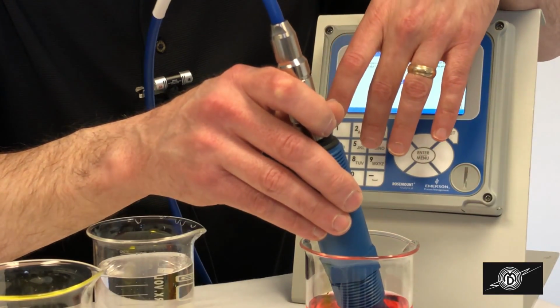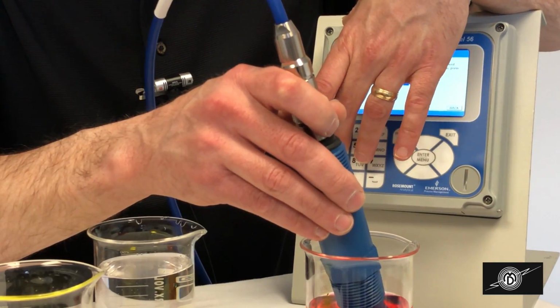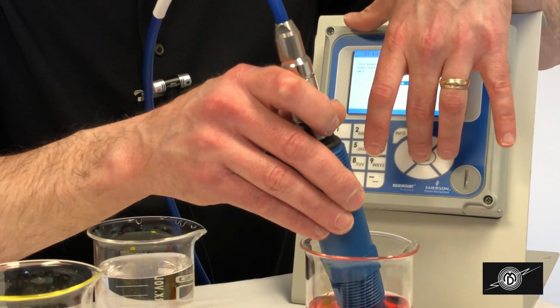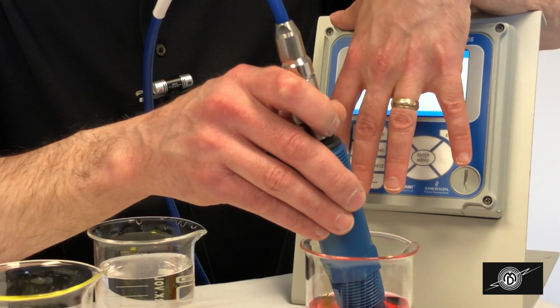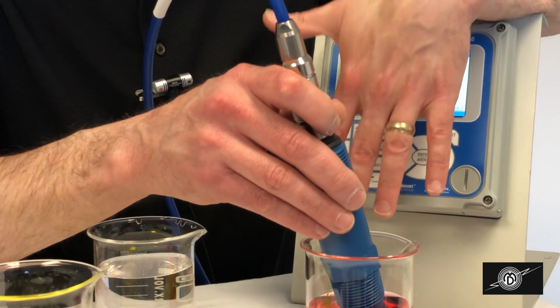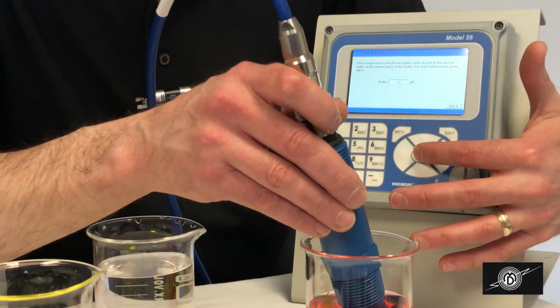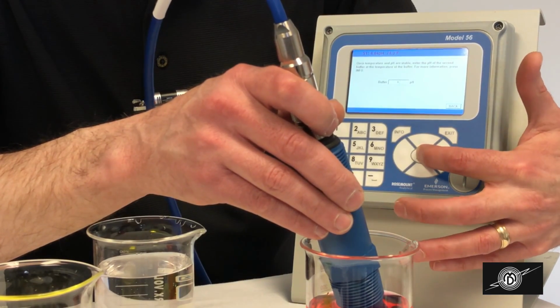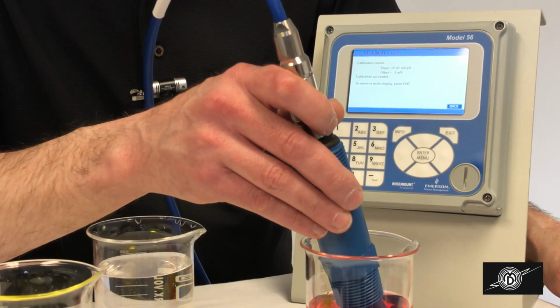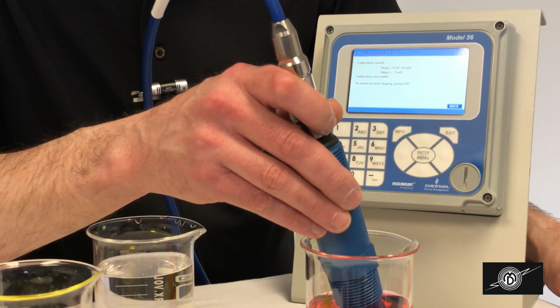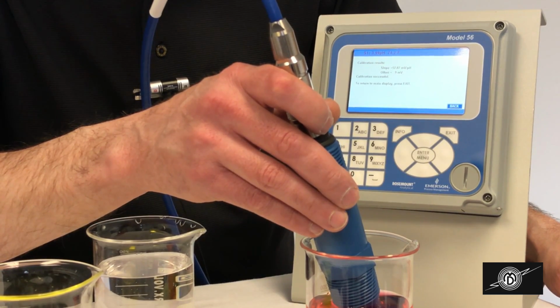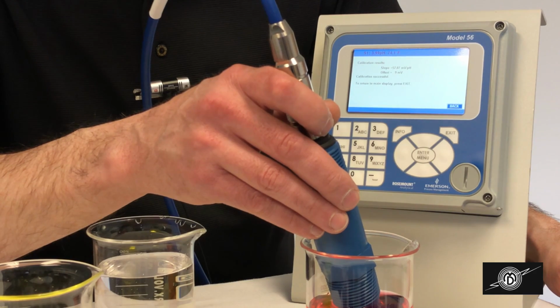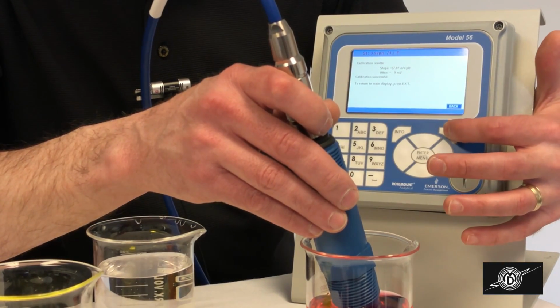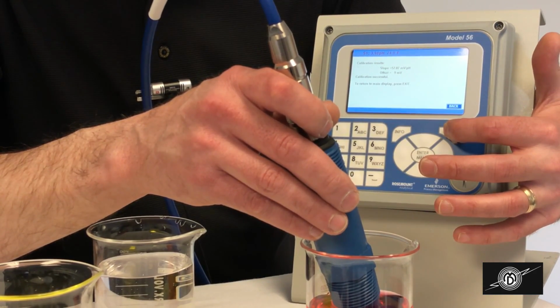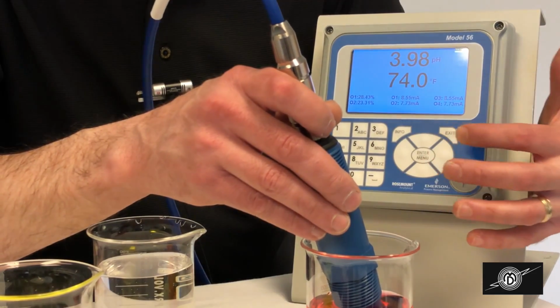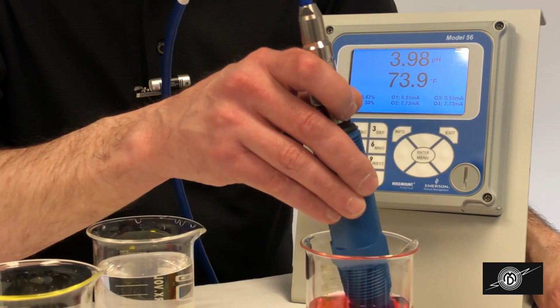And why should I use a 4 buffer or a 10 buffer when I'm doing pH? We prefer to use a 4 buffer. 4 buffer, as I said, is a positive 180 millivolts approximately. It's a stronger signal. Also, 10 buffer tends to not store well over time. So therefore, 10 buffer is a one and done. Use it once, throw it out. 4 buffer is much more stable and a stronger signal. That's why we prefer that buffer. Okay, so there we go.